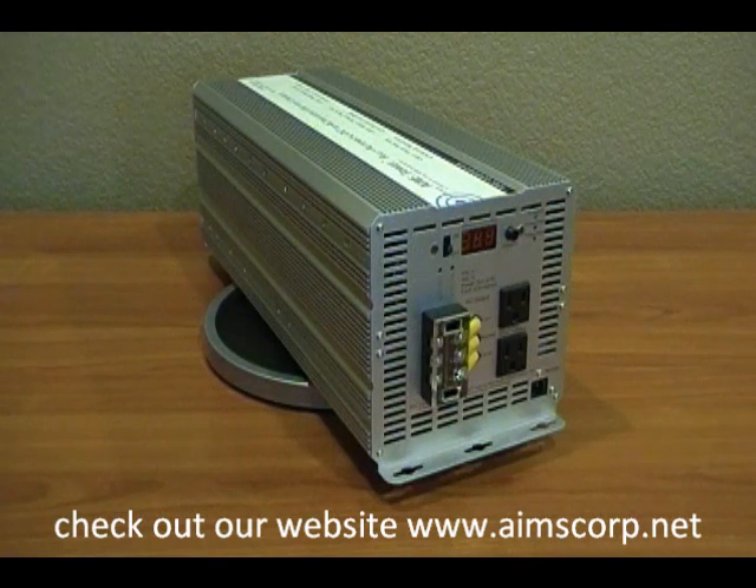It's perfect for replacing those older Heart inverter chargers that are out there in RVs today. We get a lot of customers calling in that want to find out what unit they can use to replace that, and this unit is perfect for that situation. It basically is an inverter and a converter because of the charger in there. It has the automatic transfer switch, so it will automatically sense when your generator is turned off and go back to battery power, or when you plug in shore power it will switch over. When you unplug from shore power and the batteries are fully charged, it will go back to the inverter automatically — you don't have to get up and switch any switches.